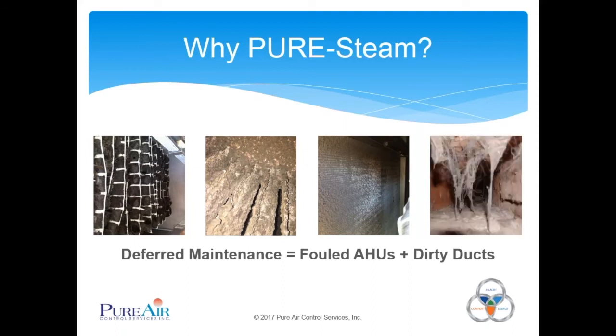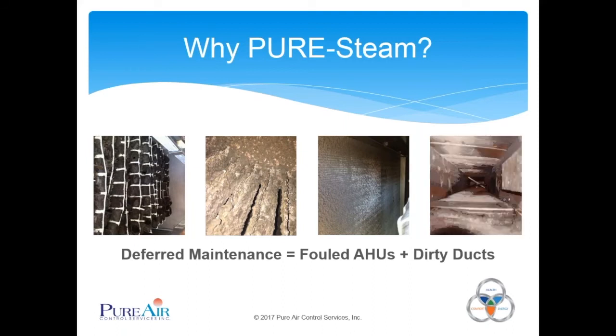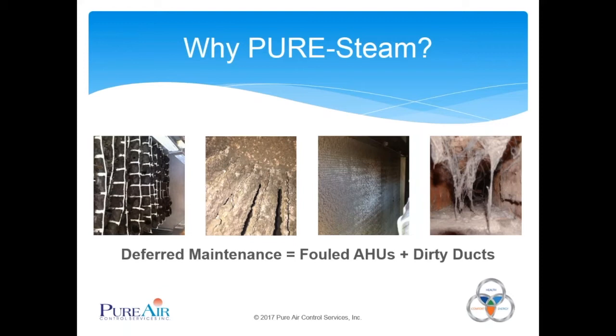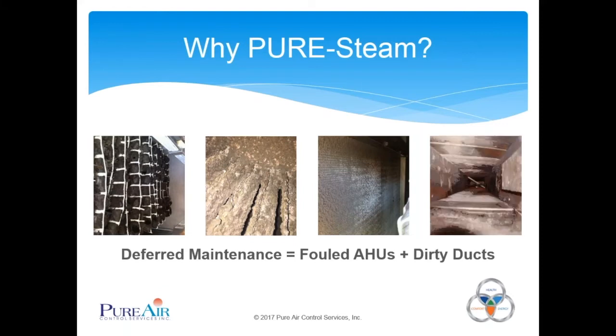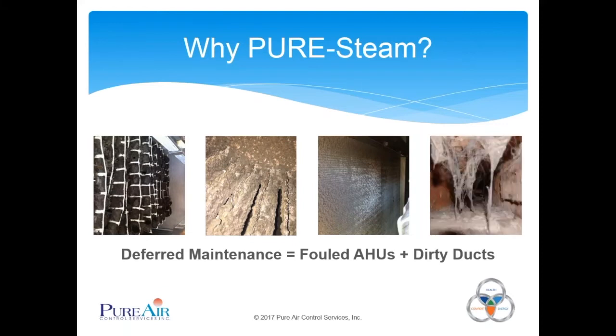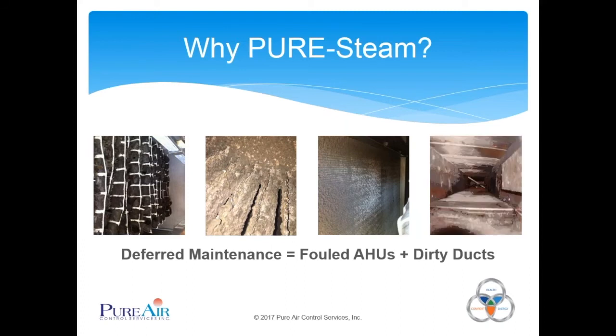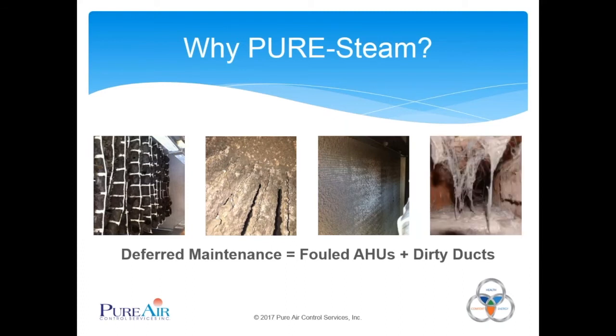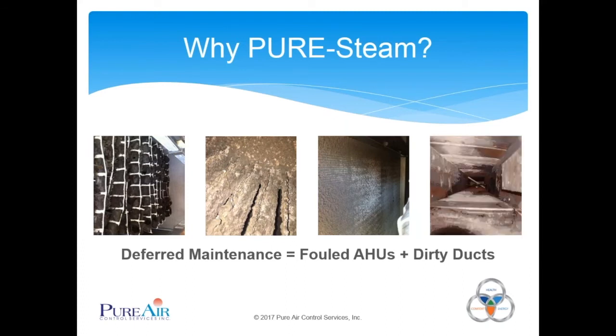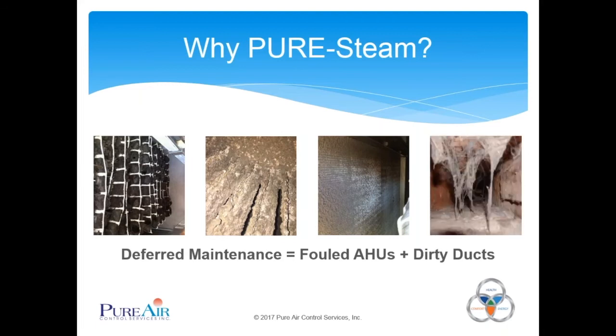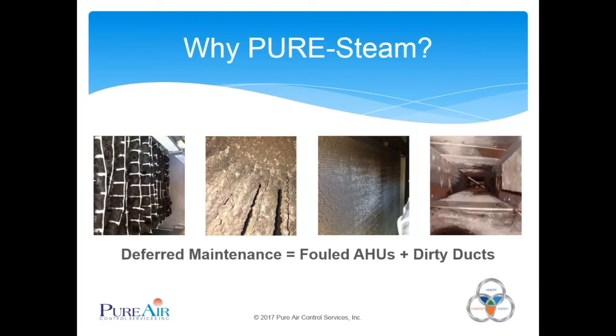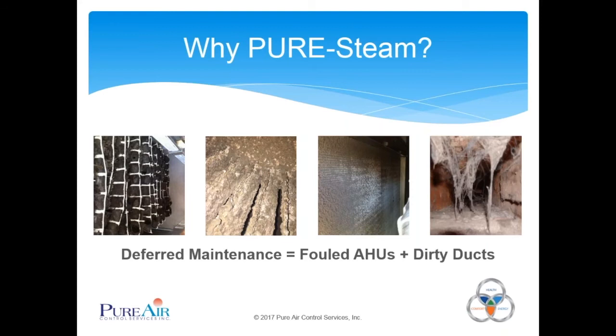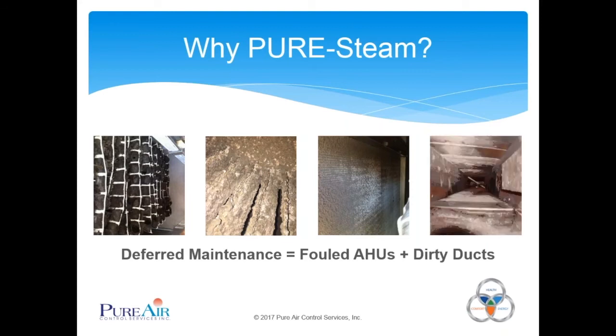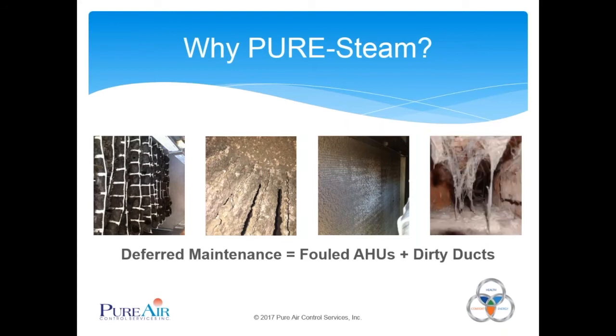You can see there's some pretty nasty stuff out there. One thing you don't think about is the fan coils or fan blades on the blower motor fan. Most of the time they're scooped to push the air. We've seen some so caked with dust that the air is just going nowhere. What's amazing is some of these pictures are from very nice places that you wouldn't realize how bad the coils and ducts look.